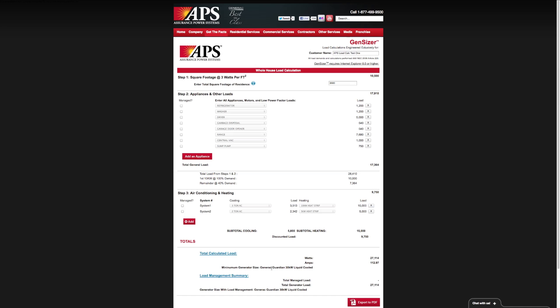Based on what I told you about load management, which is the process of managing those loads so that they don't come on during generator power, what we can do is choose those loads up here that we may want to have managed in order to minimize the size of our generator system. Let's choose maybe our dryer, which is a high heating element load, and so is the range. You can see what happens down here to the load management summary as I'm doing that. We're now managing 12,680 watts of load, and so it's reducing the size of the generator that we need.